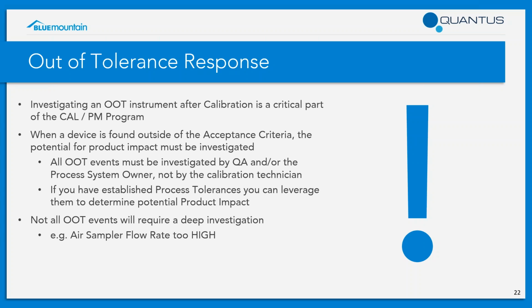And this is a real critical part of the program. So if a device is found outside the acceptance criteria, it must be investigated for potential product impact, especially if it's in the manufacturing or GLP areas and it's involved with product testing and release. And these investigations should be carried out by the QA or process system owner, not the calibration technician. The calibration technician is the subject matter expert. They can assist with the information into the investigation, but they can't lead those efforts. And again, if you have an established process tolerance, you can really leverage that to determine potential product impact.